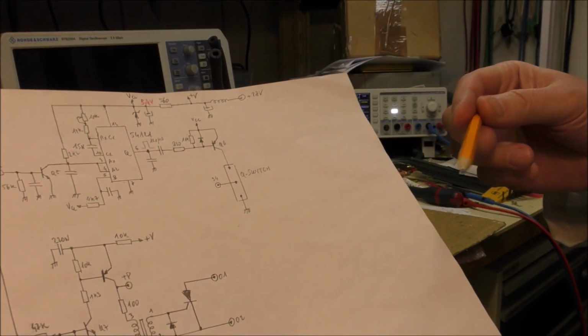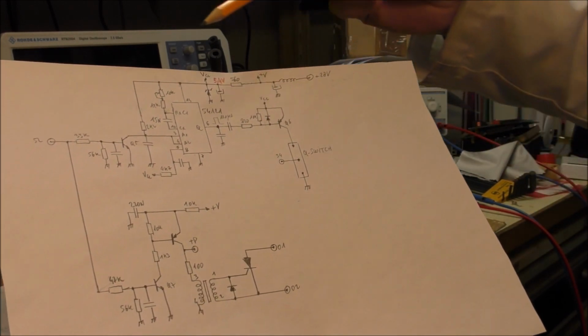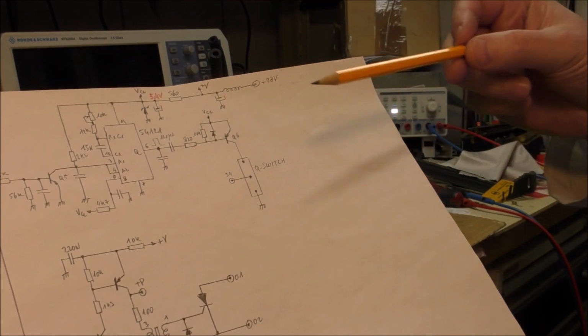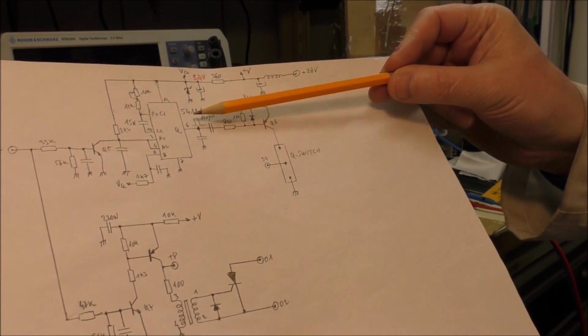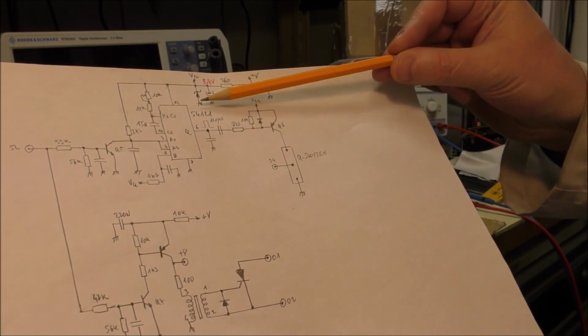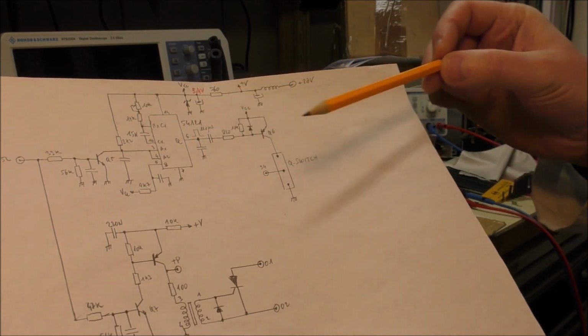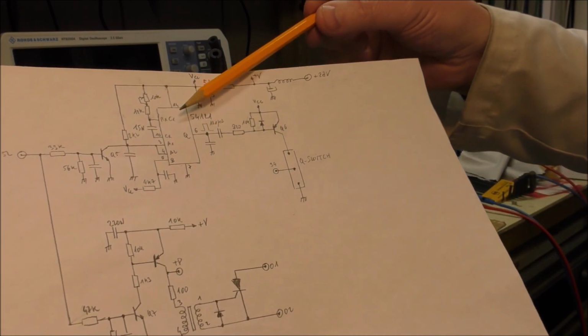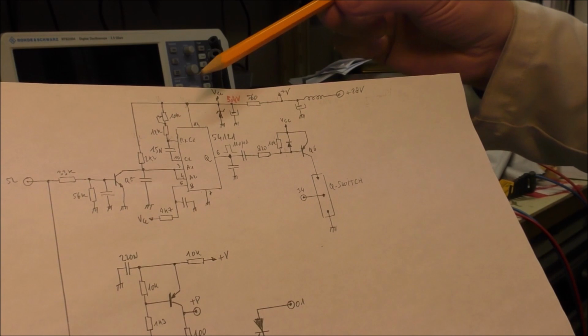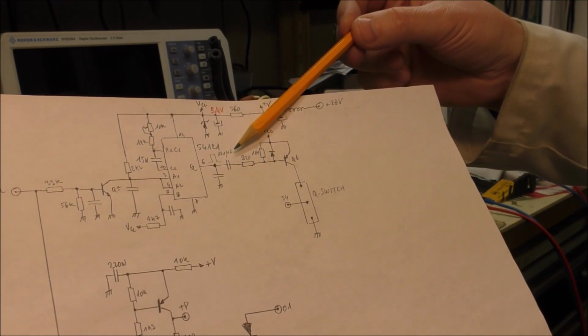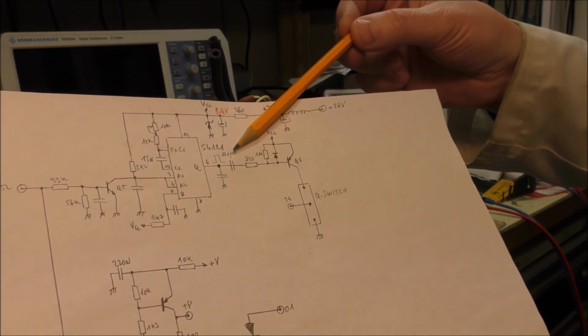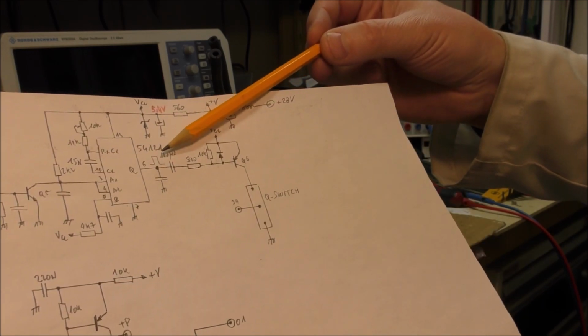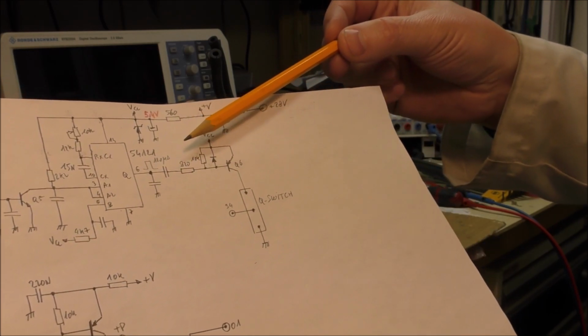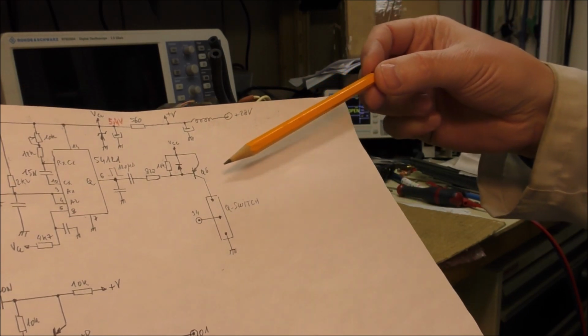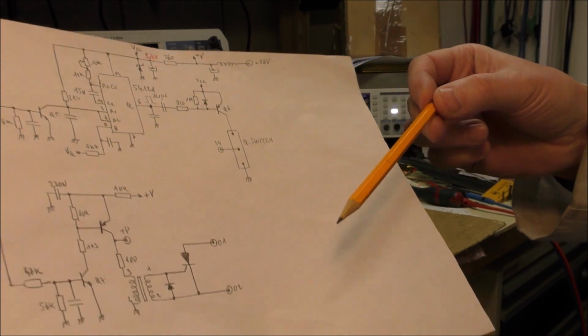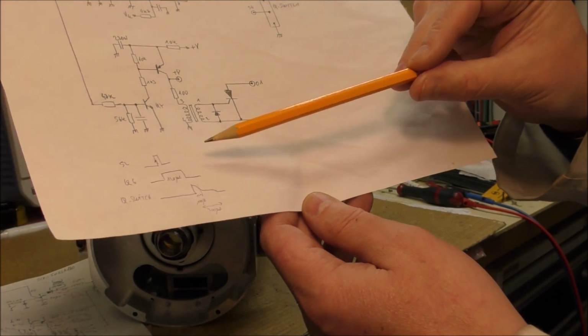The third thing is the activation of the Q switch. So the input is here. There is a delay of 120 microseconds, which uses this 121 monostable. It is possible to adjust the duration of the pulse using this trim pot here. This time permits to pump the ND-YAG crystal rod. On the falling edge of the output pulse, there is a saturation of this transistor, so this permits the activation of the Q switch. The signals are here.